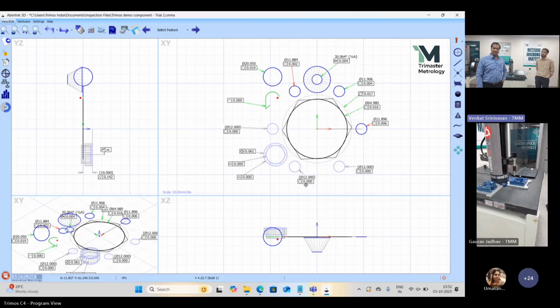We recommend annual calibration. However, ultimately, even as per NABL or any advanced quality body guidelines, calibration frequency is determined by you, the end user. If there is equipment you use in very routine fashion, you may want it inspected once a year. If it's not used so often or not subjected to much wear and tear, you could define it as once in 2 years. We've also known customers who use ring and plug type gauges very frequently, with high wear and tear, and even calibrate those at 3-month and 6-month intervals. But for this equipment in general, our recommendation is 1 year, and ultimately it's up to the customer.